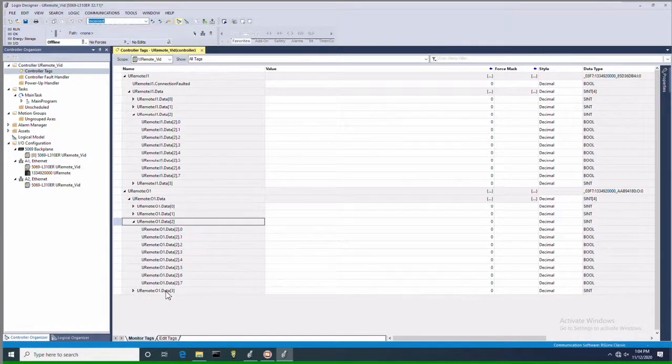So real quick, what I did is I wrote some code that basically links the first input to the first output, second input to the second output, all the way through 7. That way, if anybody wants the demo code, I can send it to you. You can see how easy this stuff is. Real quick note, if you have a bunch of input-output modules staggered within your chassis, it's going to push all the inputs together. So they're going to be sequential in the list. And then all of the outputs will be listed together. And the web server will tell you how many short integers you need to have to make that work. So that's basically it for the quick video. Let me go back to seeing my smiling face again.